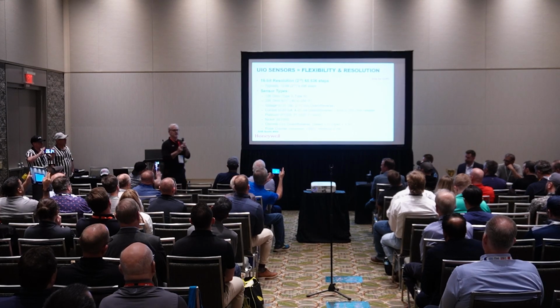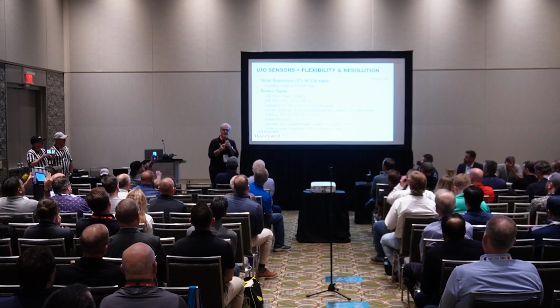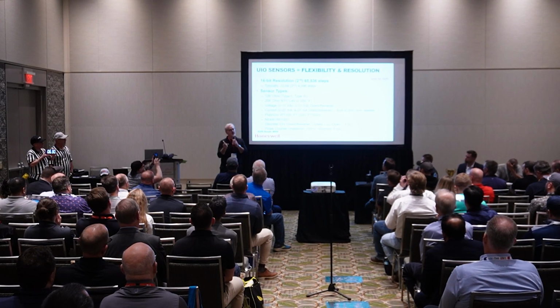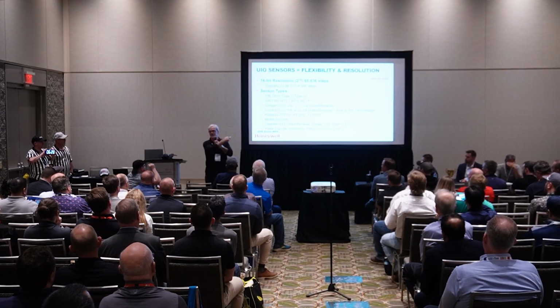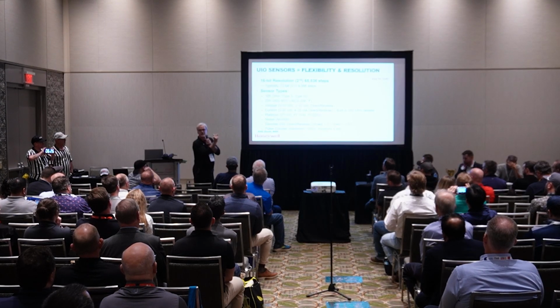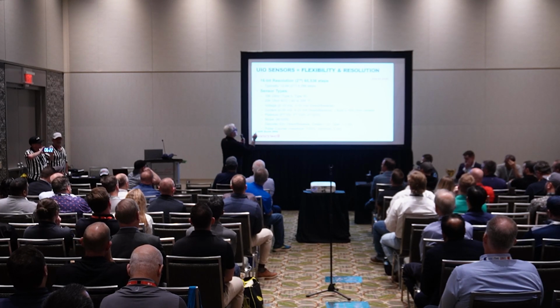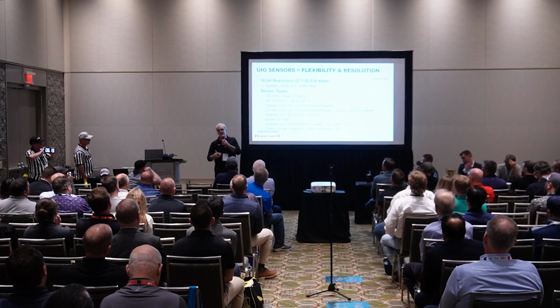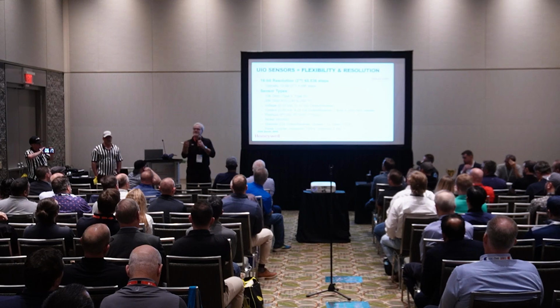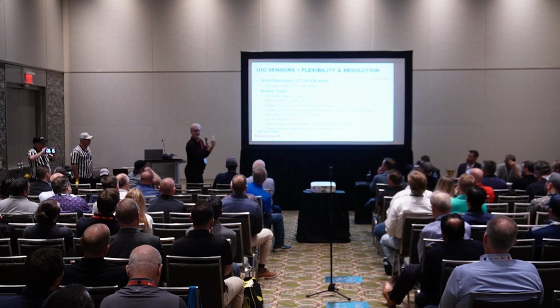The resolution. We've got 16-bit resolution on our inputs and outputs. Why is that a big deal? 65,000 increments on your input. You want tight control, I can give it to you. Most controllers are 12-bit, 4,000 increments. That's a big difference. So if you want tight resolution, I can give it to you.